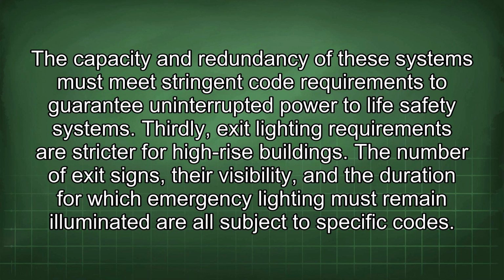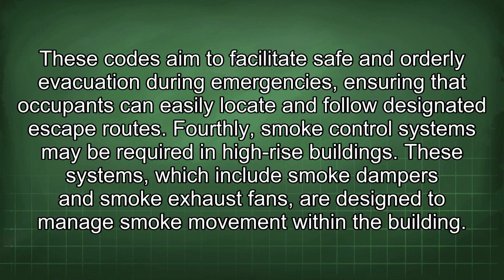Thirdly, exit lighting requirements are stricter for high-rise buildings. The number of exit signs, their visibility, and the duration for which emergency lighting must remain illuminated are all subject to specific codes. These codes aim to facilitate safe and orderly evacuation during emergencies, ensuring that occupants can easily locate and follow designated escape routes.